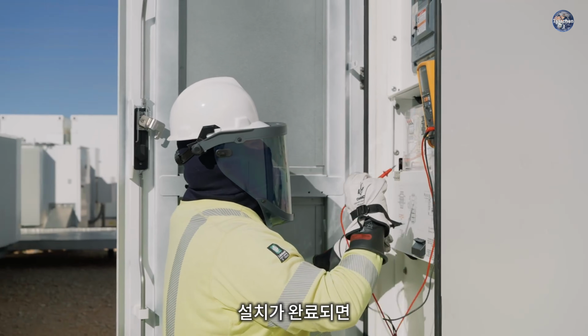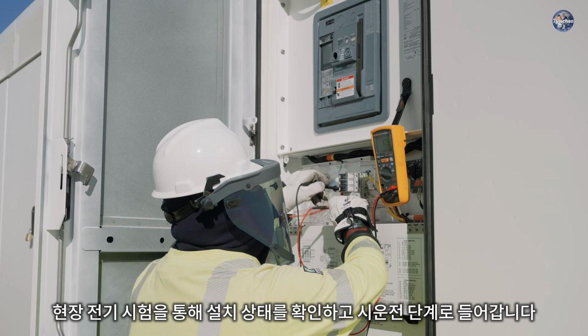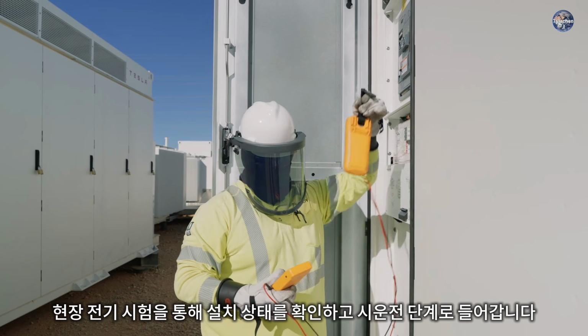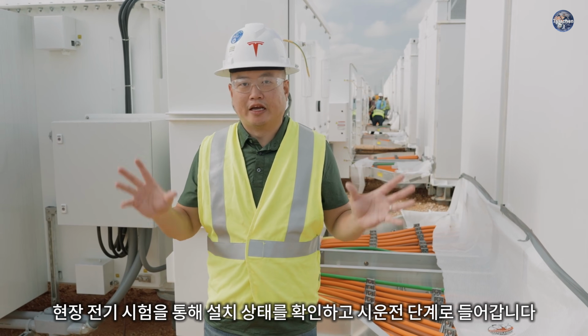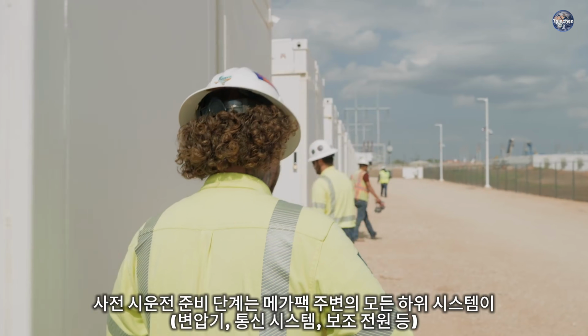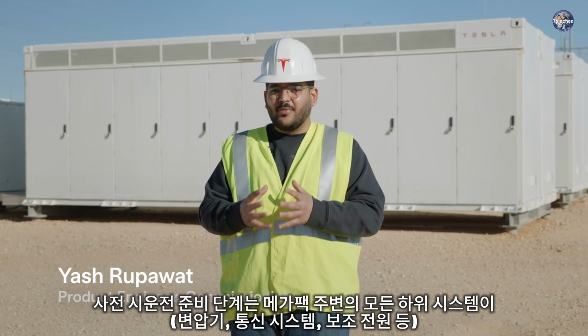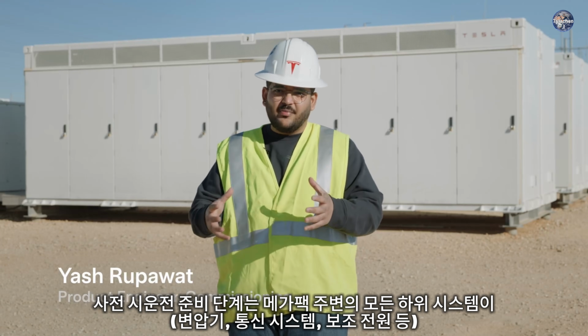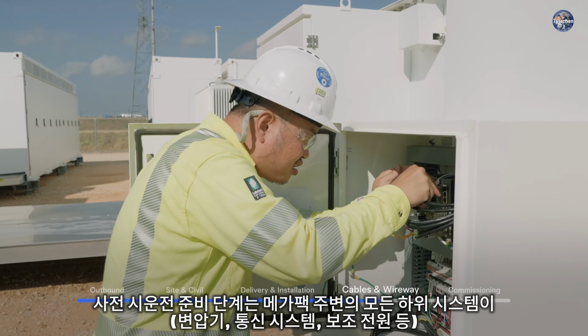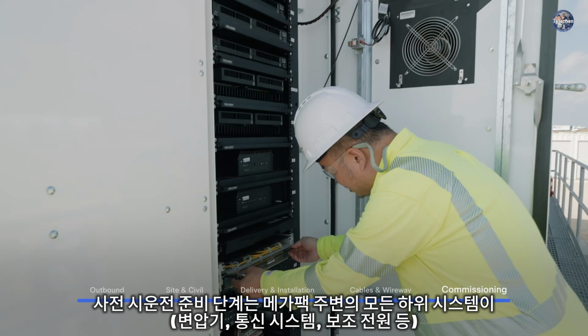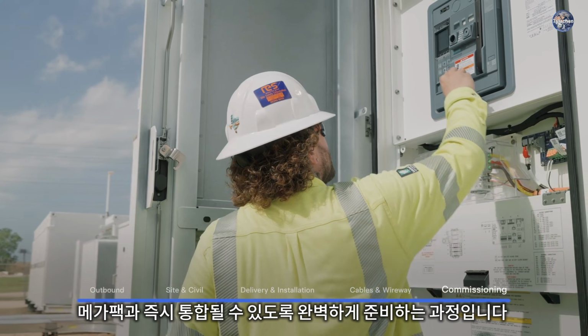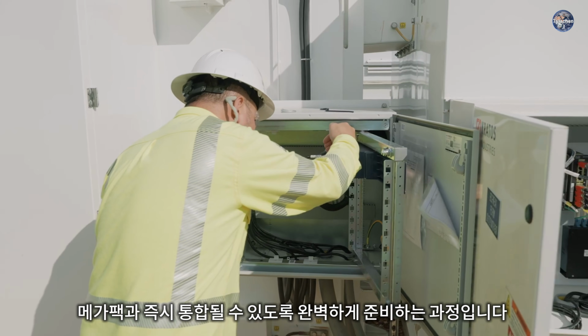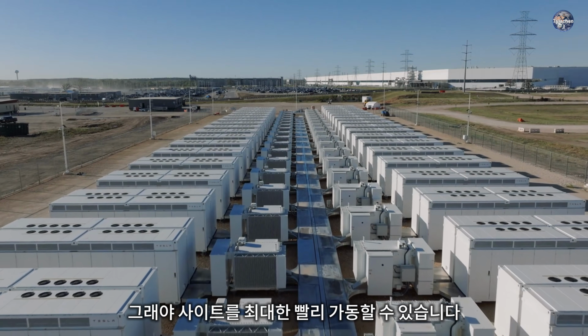After installation is complete, we go through on-site electrical testing to ensure adequacy of the installation, and then we get into commissioning. The pre-commissioning preparation phase is all about making sure that all our subsystems around the Megapacks, including the transformers, our communication systems, and our auxiliary power to the system, are all ready and primed to be integrated with the Megapacks so that our site can be up and ready as soon as possible.